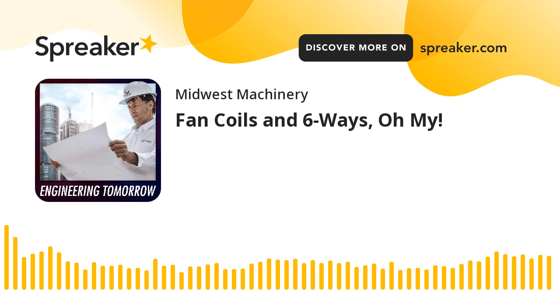So you guys, looks like you're also making blower coil units and air handling units. You want to tell me about that a little bit? Yeah, the blower coils we've had for several years. The industry as a whole is going away from a belt-driven blower coil. Belt-driven blower coils are obviously, as their name implies, using belts and shims and sheaves to adjust the actual CFM on units. They're good at overcoming static.